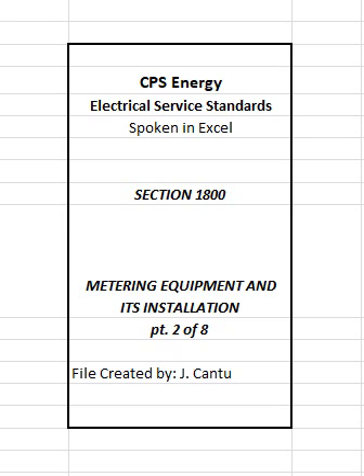2. Code 11, 50 inches H x 32 inches W x 14 inches D, for 3 to 500 kcm/phase or equivalent kcm in fewer conductors. 3. Code 12, 60 inches H x 48 inches W x 14 inches D, for 4 to 750 kcm/phase or equivalent kcm in fewer conductors. Note 1. The total kcm value of the service conductors listed for any enclosure above shall not be exceeded. Note 2. Code 12 enclosure may be adapted for busbar installations, but busbars shall not have an ampacity larger than 2000 amperes or a width greater than 4 inches.